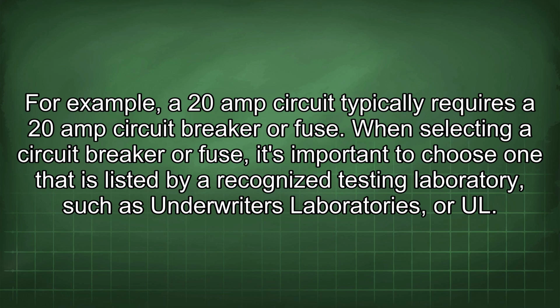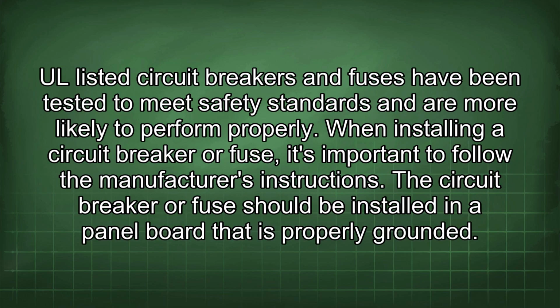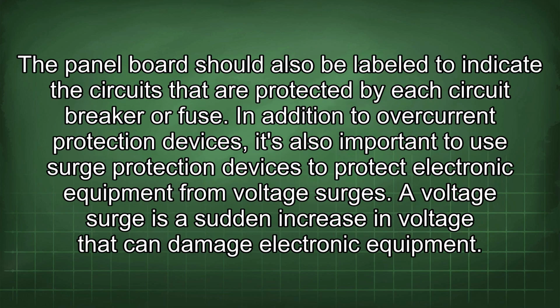When selecting a circuit breaker or fuse, it's important to choose one that is listed by a recognized testing laboratory, such as Underwriters Laboratories, or UL. UL-listed circuit breakers and fuses have been tested to meet safety standards and are more likely to perform properly. When installing a circuit breaker or fuse, it's important to follow the manufacturer's instructions. The circuit breaker or fuse should be installed in a panel board that is properly grounded. The panel board should also be labeled to indicate the circuits that are protected by each circuit breaker or fuse.